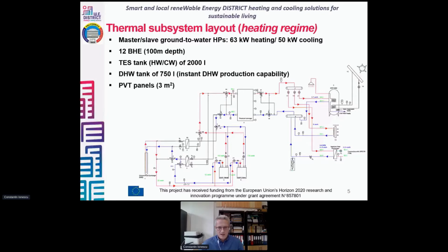During the heating period, the heat produced by the heat pumps is stored in a 2,000-liter storage tank. From here, by means of a distributor, the heat produced is distributed to the heating system of the building, to the domestic hot water preparation tank, and to the heat exchanger for injection into the local district heating.